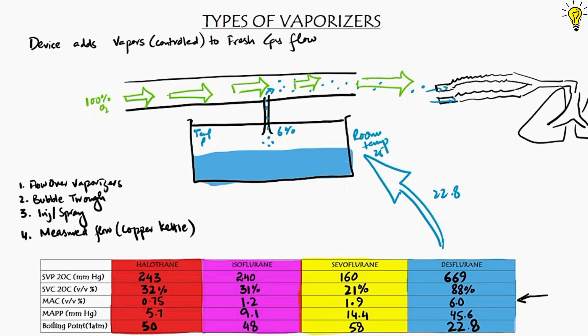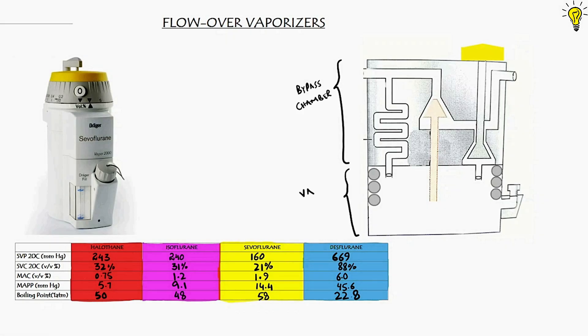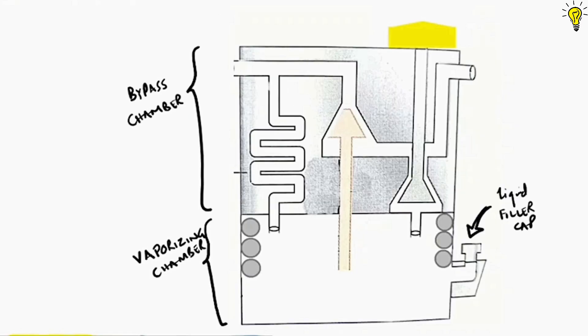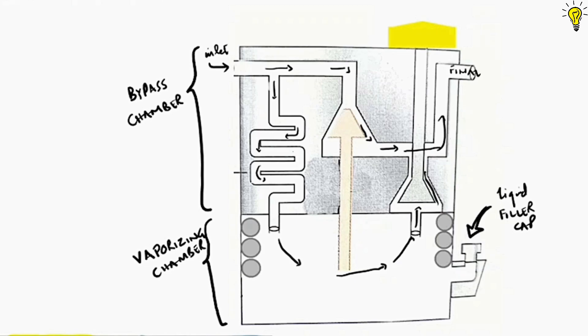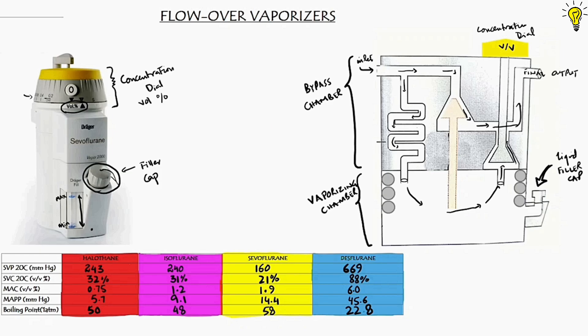Now, this is the basic working design of flow-over vaporizers. Different machines have different layouts, but the basic principle of variable bypass is the same. It has two main chambers: the bypass chamber and the vaporization chamber. There is a liquid filling cap and an indicator showing liquid level in the vapor chamber. The concentration dial above allows you to set a specific volume percentage of vapor desired in the final output. Wicks help maintain temperature by gathering heat from surroundings. Finally, there is a temperature-compensating cone or bimetallic strip that assists with temperature compensation.